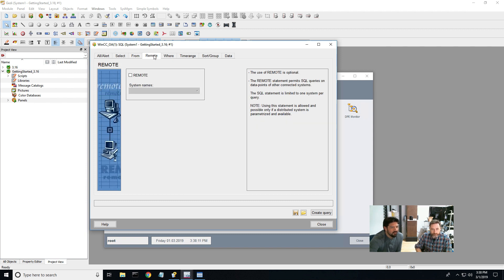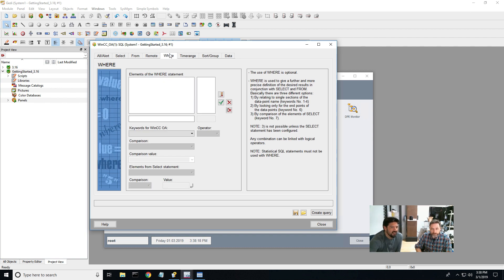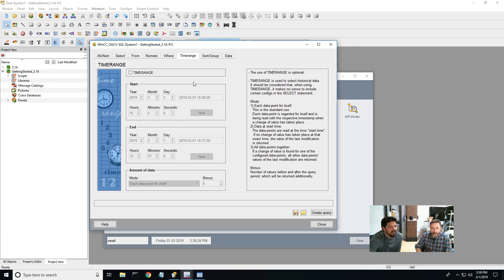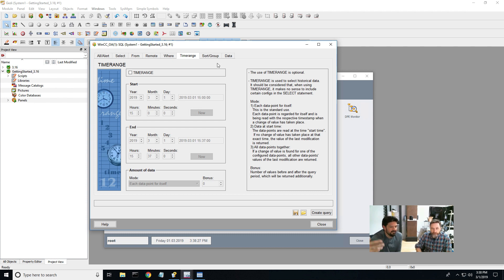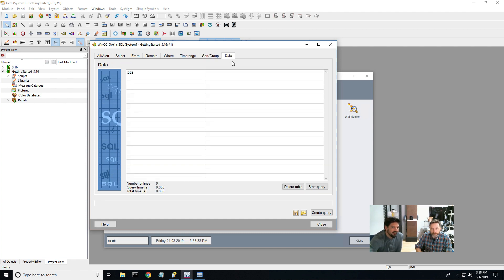I'm going to hit OK. I'm going to click this button and move it to the from statement, hit the check mark. And then remote, this is for if we've got a distributed system and I want to run a query and grab data from a distributed remote WinCC OA station. Where, I'm not going to do a where statement because there's some comparison values in here, but you can do that. Time range, I'm just going to leave that blank. We're just going to pull all data for however long I've had this running. Sort group, not going to touch this either.